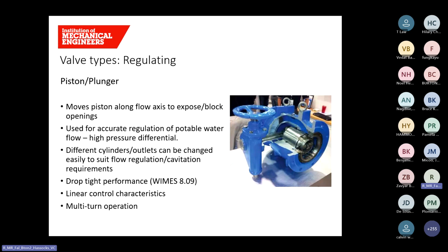Another regulating valve is the piston or plunger valve. In this valve, there's a piston that moves along the flow axis, and it blocks or exposes openings which allow more or less flow to pass. They're typically used for flow regulation of potable water, particularly where there's a high differential across the valve. There are additional features that can be installed, such as the anti-cavitation device on the outlet of the valve. These valves also offer drop-tight performance. They also have linear control characteristics similar to that of the eccentric plug valve, and they are multi-turn operation.